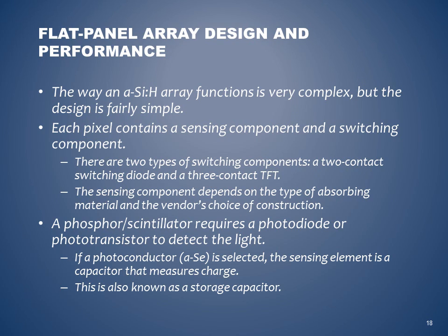A phosphor scintillator requires a photodiode or phototransistor to detect the light. If a photoconductor, a-Se, is selected, the sensing element is a capacitor that measures charge. This is also known as a storage capacitor.